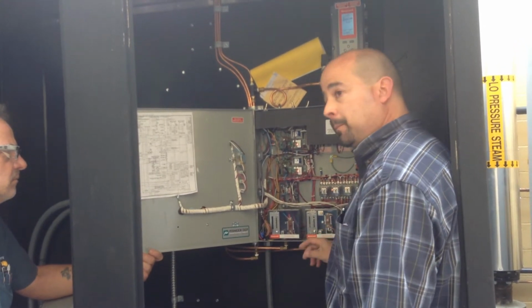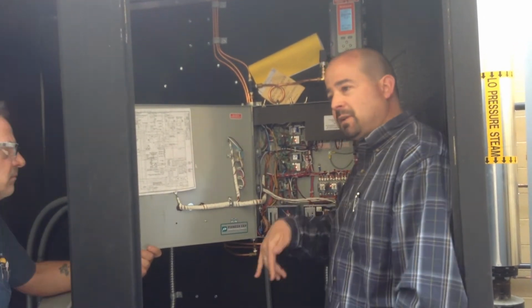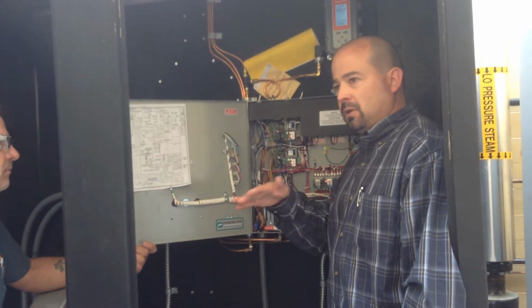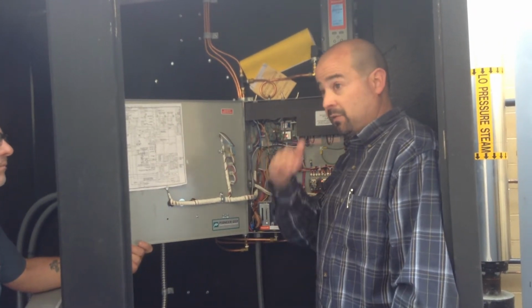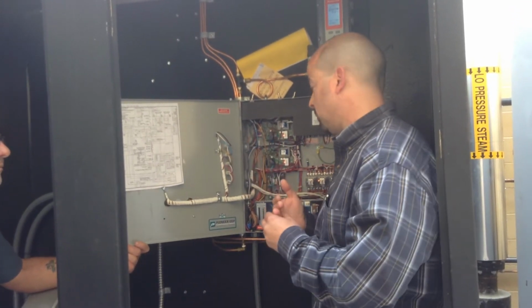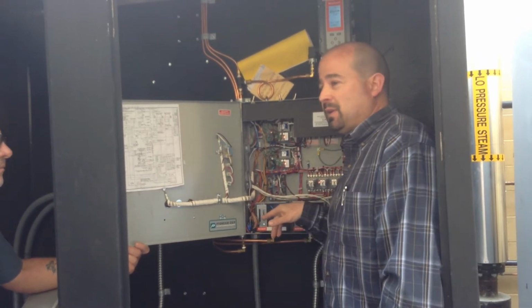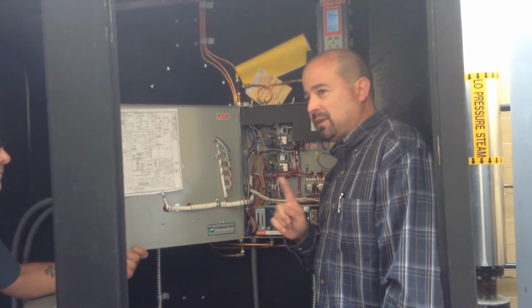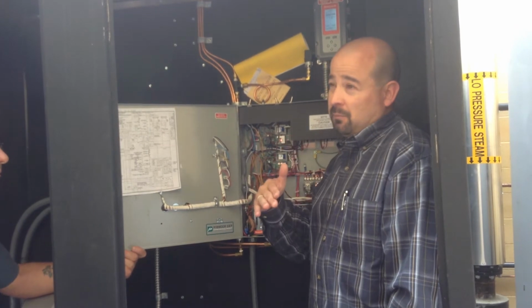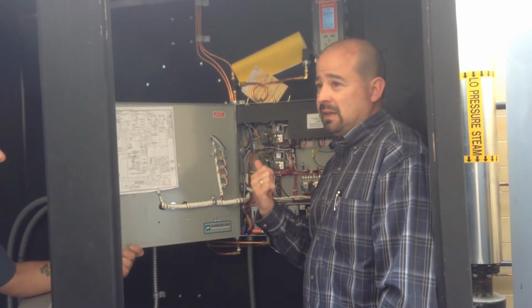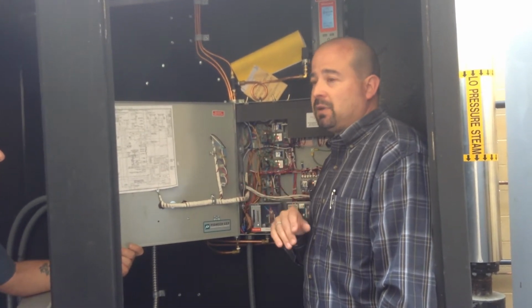You get how many PSI? 15. This is a 15 PSI boiler. The definition between high pressure and low pressure is 15 PSI. So this is a low pressure steam boiler. But just because it's a 15 PSI boiler doesn't mean you can run at 15 PSI. You have to run it 10% below the safety relief valve setting. So 13.5 PSI max.